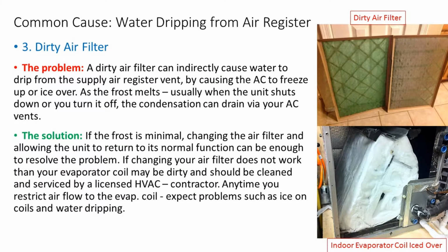A dirty air filter puts a restriction on the fan. If it's dirty, if it's a plastic bag. I actually did a trouble call one time. She says, "Oh, I think my air conditioner needs some Freon." I said, "Okay, ma'am, I'll be out there." This was when I was a Trane dealer, servicing air conditioners. I got out there, it was a Walmart plastic bag that was stuck inside the coil. I pulled it out, refrigerant levels were fine, ice went away.